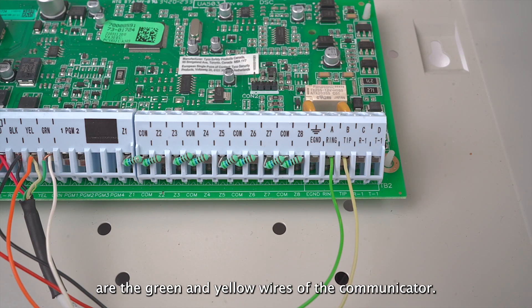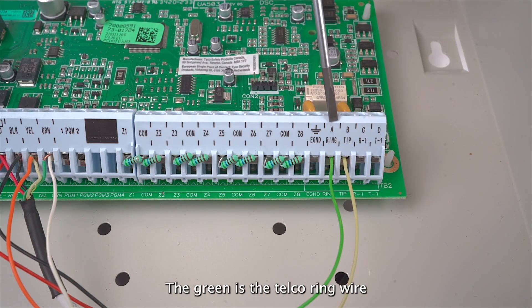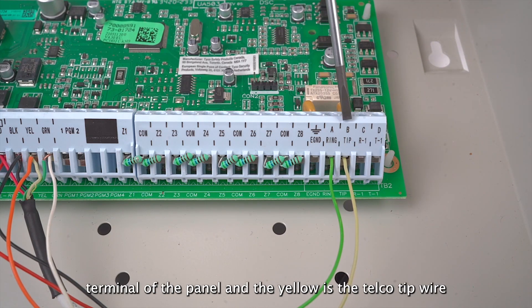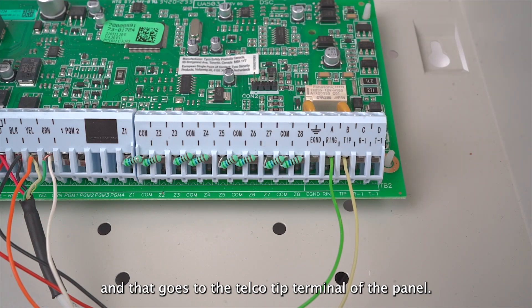The last two wires that we have are the green and yellow wires of the communicator. The green is the telco ring wire and that goes to the telco ring terminal of the panel, and the yellow is the telco tip wire and that goes to the telco tip terminal of the panel.